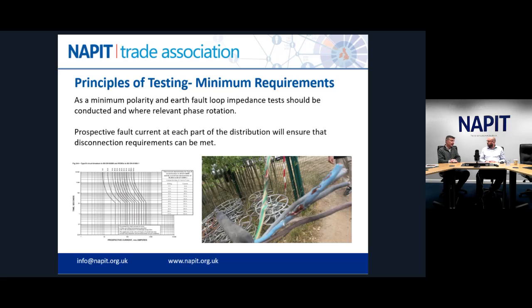The other thing is we need to do the short circuit current as well, because with long extension leads, it's easy to forget that if I've got an RCD protected circuit, the earth fault loop impedance can actually be quite high. But if there's a short circuit, then we can give rise to the risk of fire. So BS 7909 requires short circuit current to be checked as well. Yeah, because the RCD will only be there for an earth fault. Absolutely. We've got the image there, the cable's been damaged.